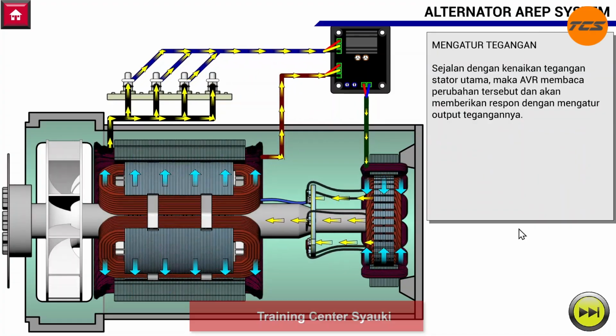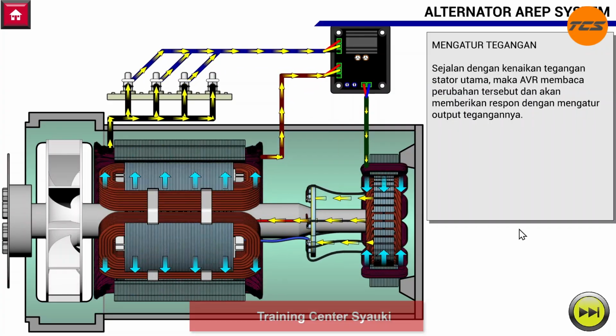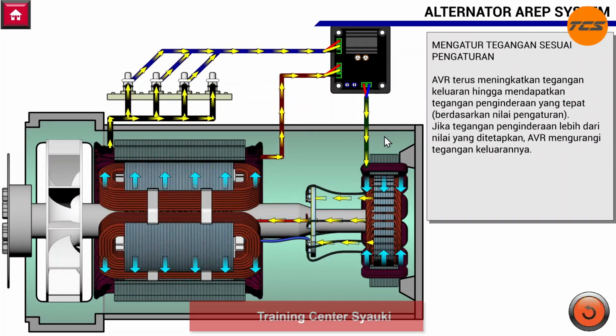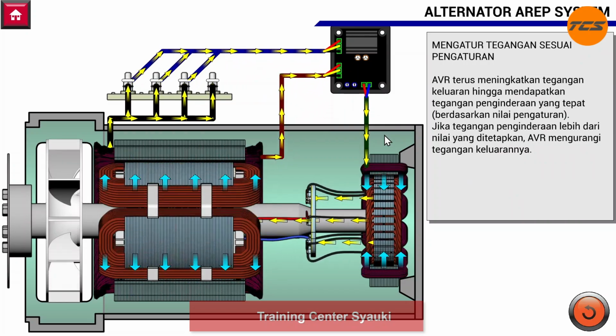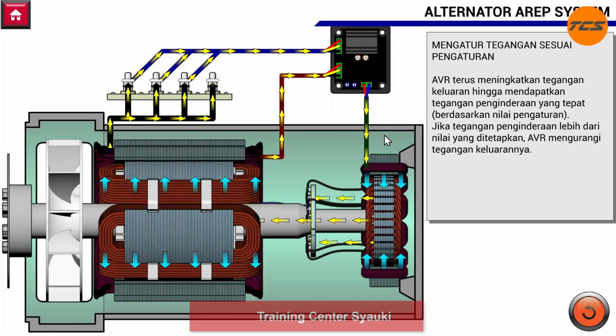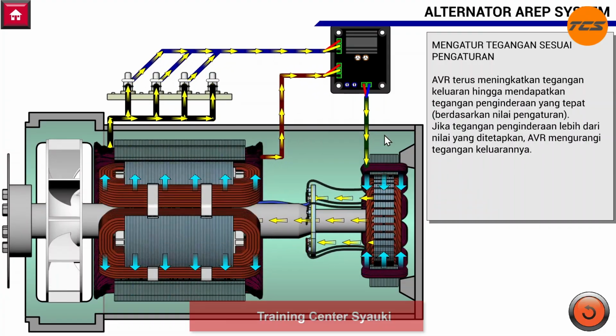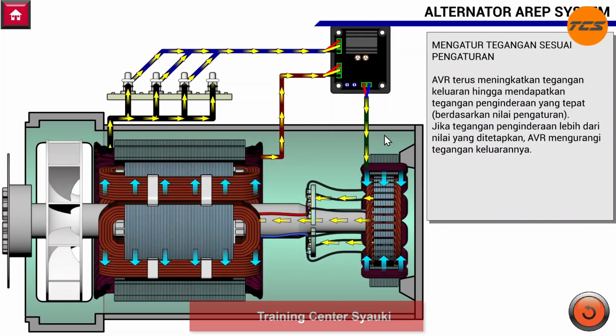As the output voltage rises, the AVR continuously monitors the sensing voltage. If the sensed voltage is lower than the AVR set point, the AVR increases its output current to the exciter stator. For example, if the AVR is set to supply 8 volts DC and the output voltage is still low, the AVR will increase the excitation current by increasing the excitation voltage. Once the sensed voltage reaches the set point, the AVR stabilizes its output. For instance, it will maintain a constant voltage to the exciter stator.